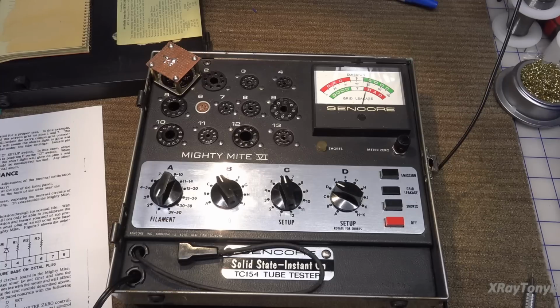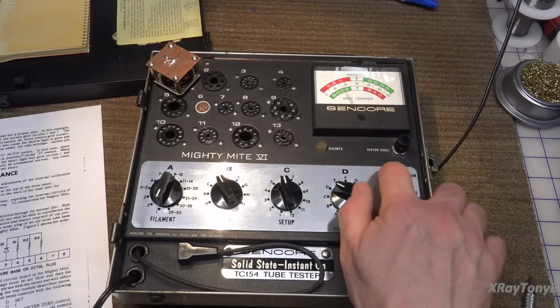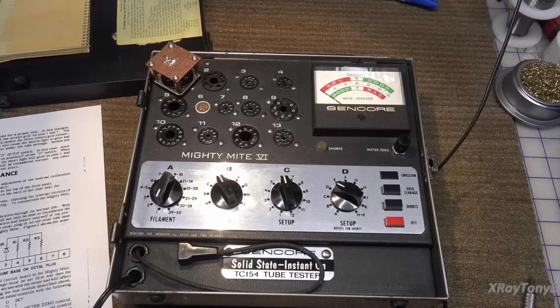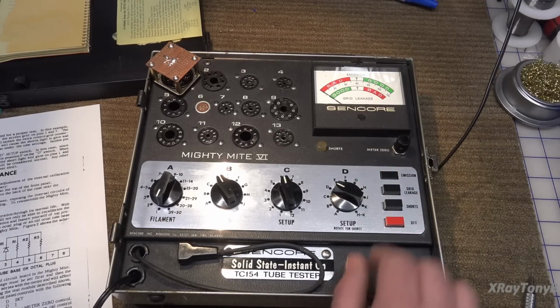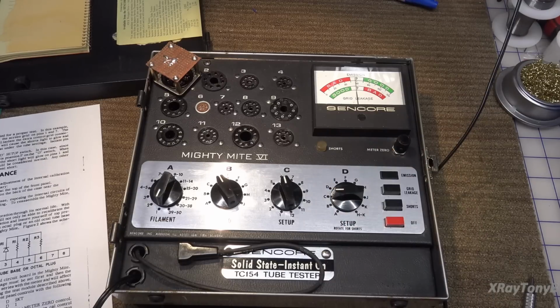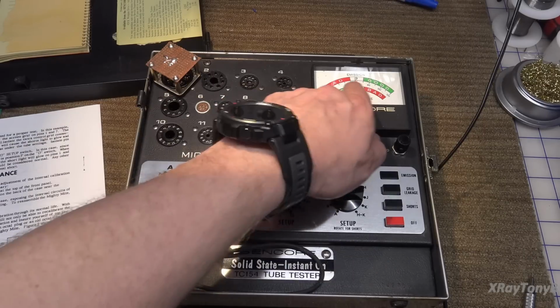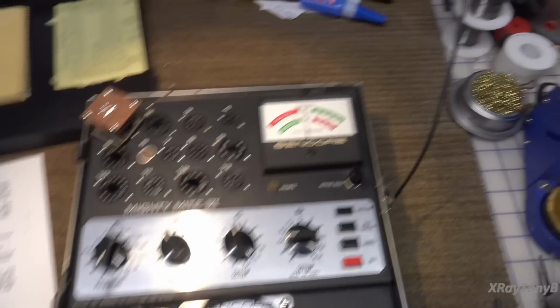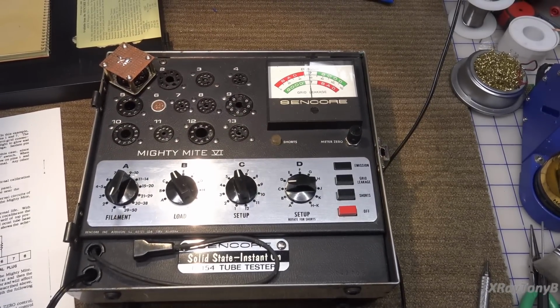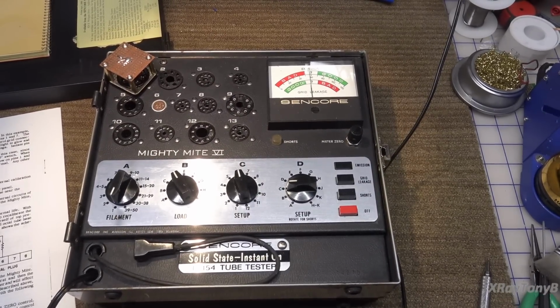And then the emissions calibration, we want to hit the emission button, and we want to move this to C, and it says the meter should read 60. And it's pretty close, but it's off by a little bit. See that? So we're going to have to take this out of the case and make the adjustments.